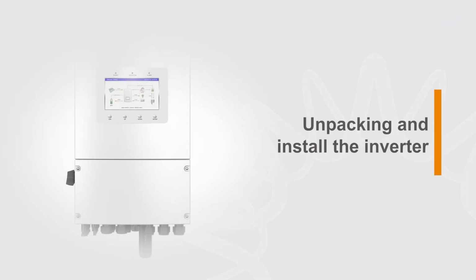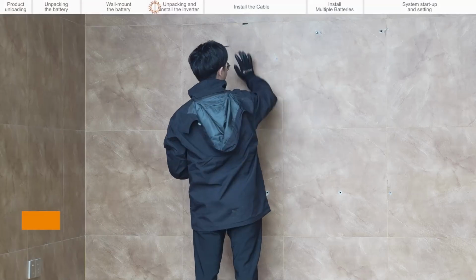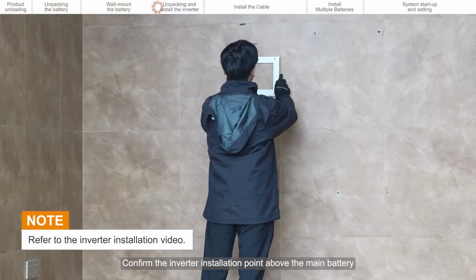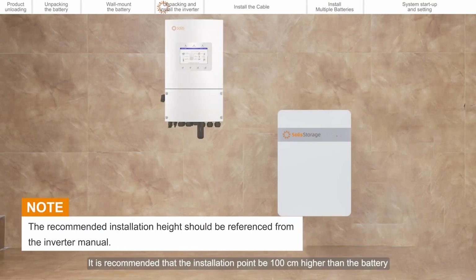Unpacking and install the inverter. Confirm the inverter installation point above the main battery. It is recommended that the installation point be 100 centimeters higher than the battery.